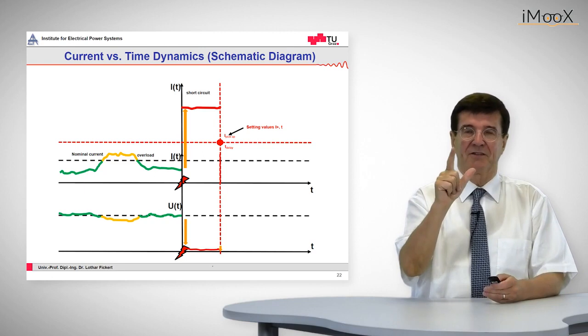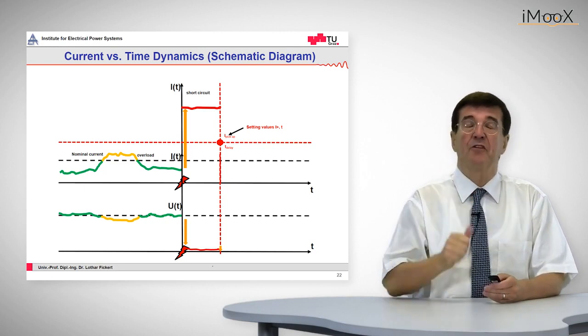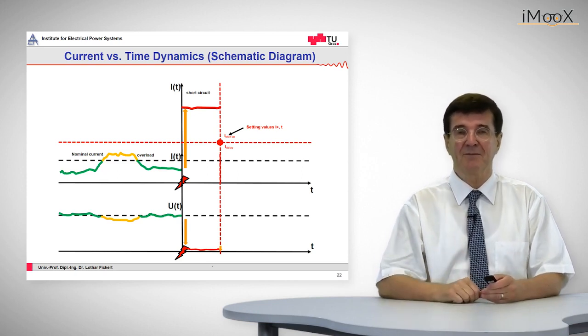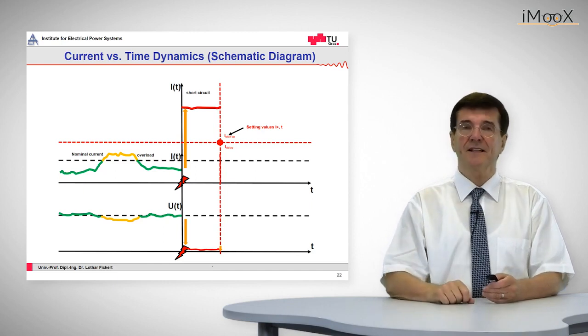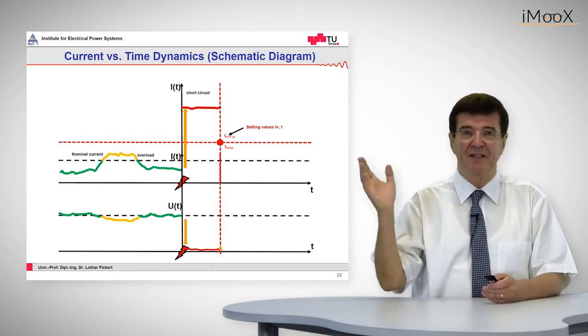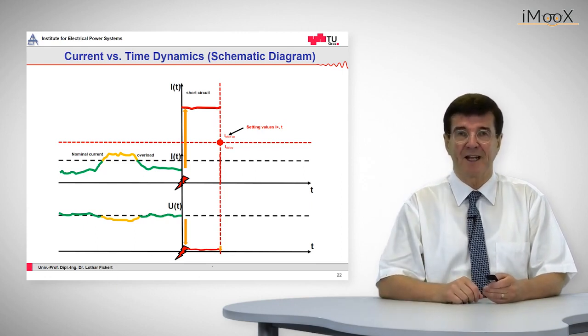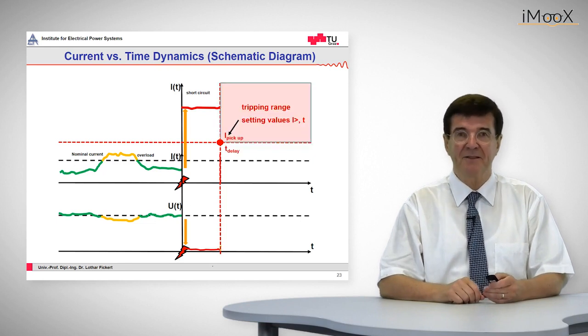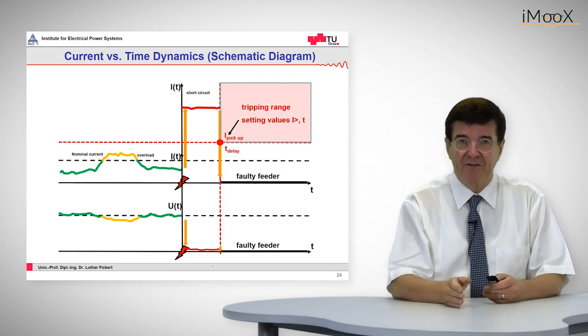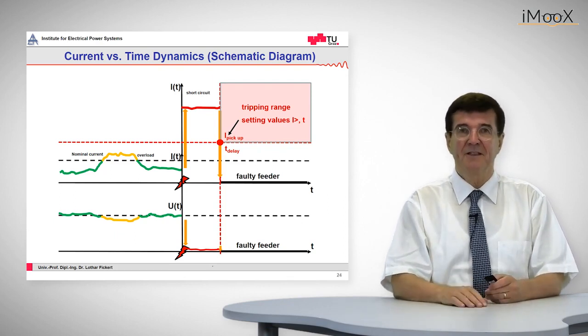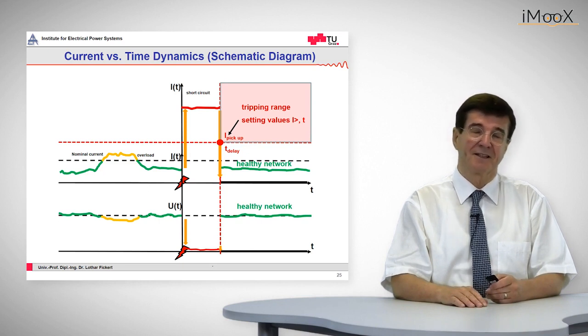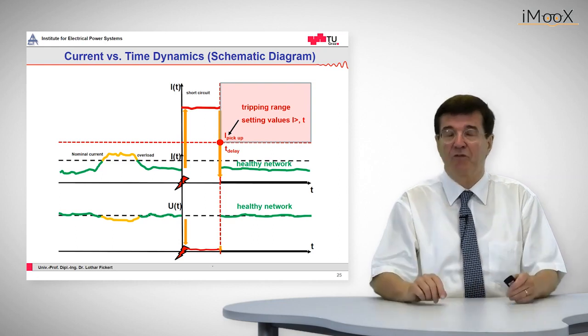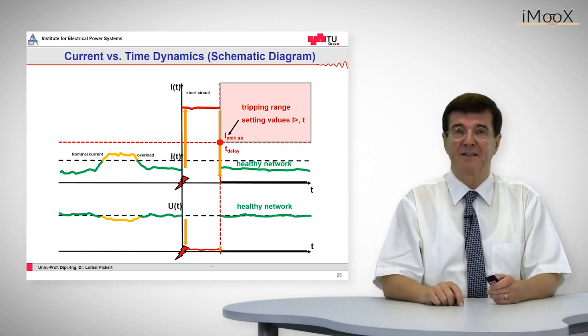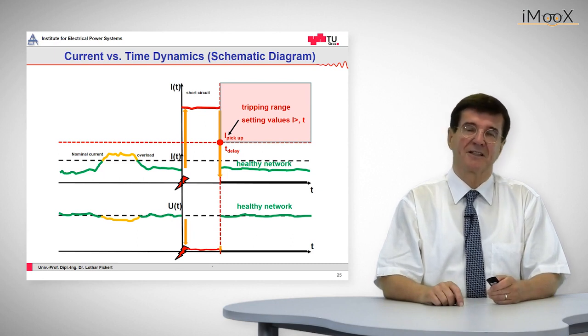The protection has two setting values which are relevant at this point. The first is the pickup value, which is of course below the 5 kiloamps, so that the protection sees there is a short circuit. And the second one is a time delay. The time delay, for example, is given here as 0.4 seconds, and when this time has elapsed, then the protection device will trip the circuit breaker. The current will go down to zero, since the circuit breaker has opened the faulty feeder, and the voltage on the faulty line, of course, goes down to zero. And the voltage in the healthy network, in the other feeders, has recovered since there is no fault anymore in the grid, and the current in these healthy feeders, by the way, is more or less the same as before. So this was the voltage and current dynamics versus time.